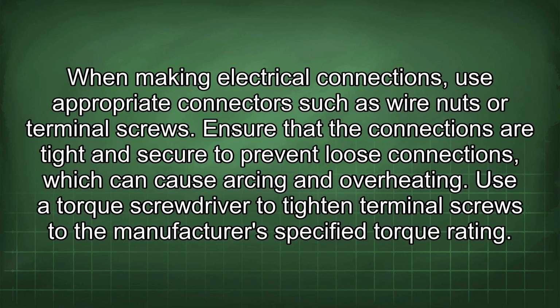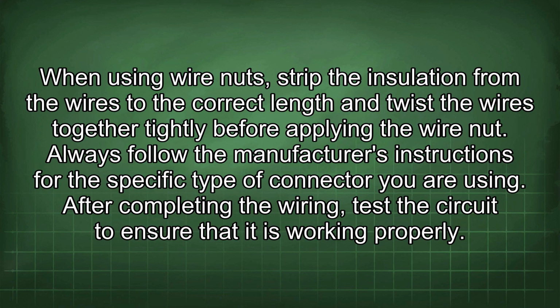When making electrical connections, use appropriate connectors such as wire nuts or terminal screws. Ensure that the connections are tight and secure to prevent loose connections, which can cause arcing and overheating. Use a torque screwdriver to tighten terminal screws to the manufacturer's specified torque rating. When using wire nuts, strip the insulation from the wires to the correct length and twist the wires together tightly before applying the wire nut. Always follow the manufacturer's instructions for the specific type of connector you are using.